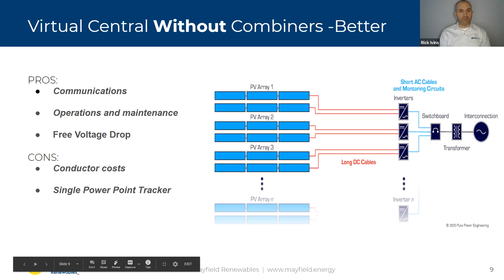What was a con in the previous was running communication over long distances between inverters spread all over. Now, if you take those inverters and put them all next to each other on the same pad or rack, the monitoring probably doesn't even need to go underground. Those communication circuits can just daisy chain these inverters, spaced as far apart as needed for ventilation.